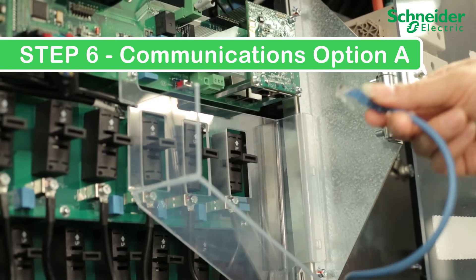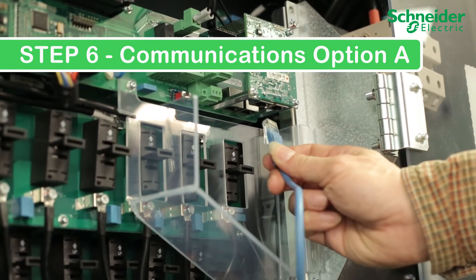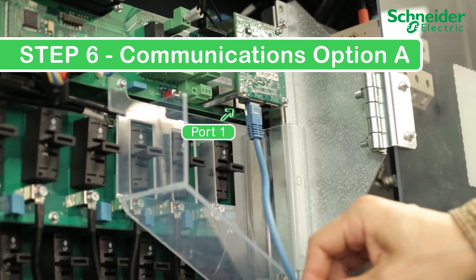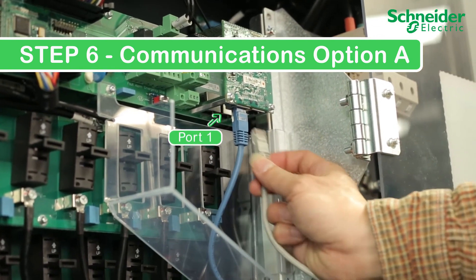Step 6: Communications option A. Make your Ethernet connection. For star topology or end of daisy chain connections, connect to port 1. For mid-string CL60s in a daisy chain, connect the second cable to port 2.